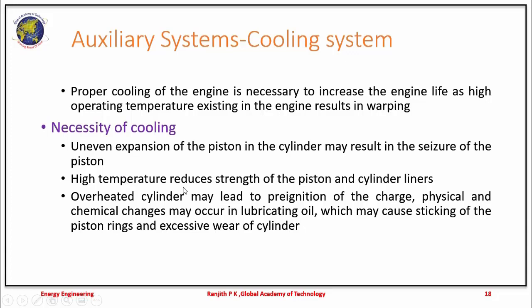Then high temperature reduces the strength of the piston and cylinder liners over a period of time when the system is in continuous operation. And the overheated cylinder may lead to pre-ignition of the charge and cause physical and chemical changes in the lubricating oil, which makes this lubricating oil stick to the piston rings and causes excessive wear of the cylinder.